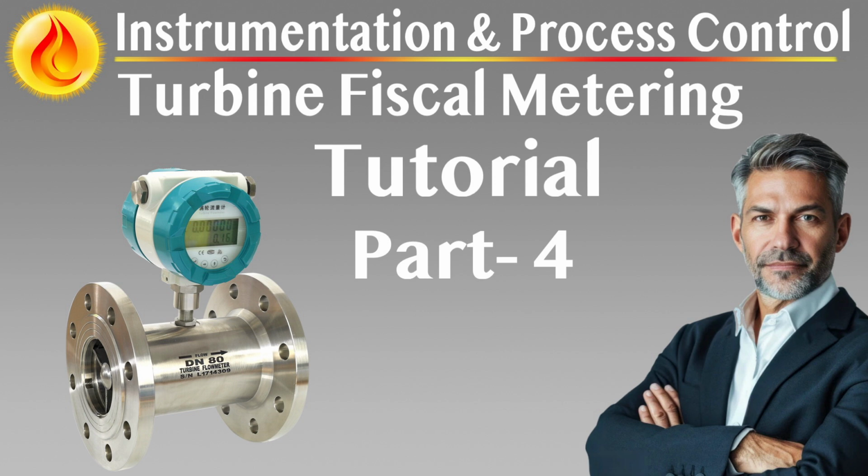Calibration must be traceable to national or international standards, and when possible, performed with fluid properties similar to the intended process conditions. If testing with process fluid is not feasible, calibration using water is acceptable, provided the manufacturer supplies validated correction factors for fluid viscosity and density. The prover system must also be calibrated by an independent, accredited laboratory and must meet traceability requirements to establish its reference volume. Witnessed verification by the principal or metrology authority is often required and must be documented on a formal certificate.